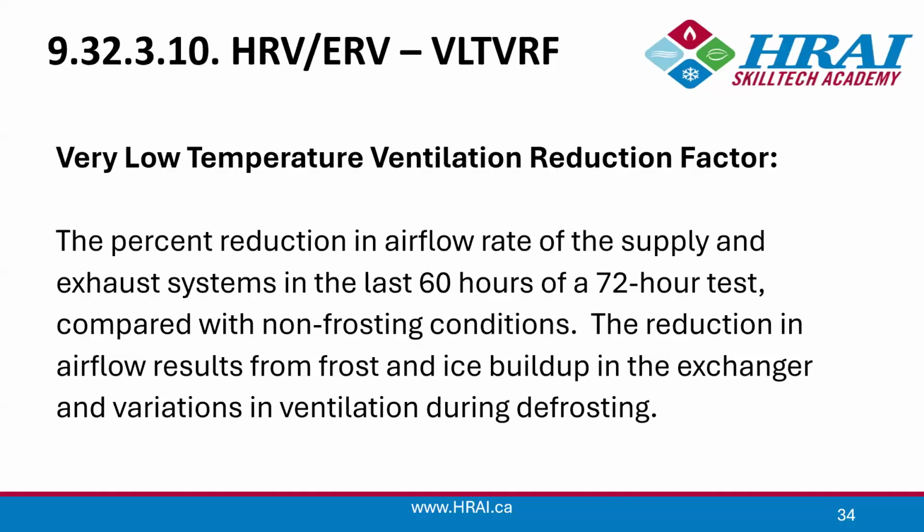So that's the reasoning there. So less than 50%. You can't choose an HRV that has more than 50% very low temperature ventilation reduction factor. So that means half the time it's not working. So we don't want that. We want it working in cold temperatures. So keep the numbers down.